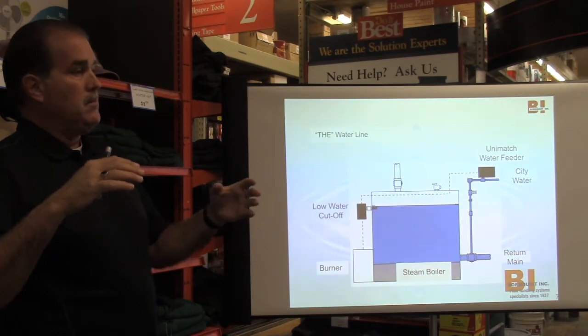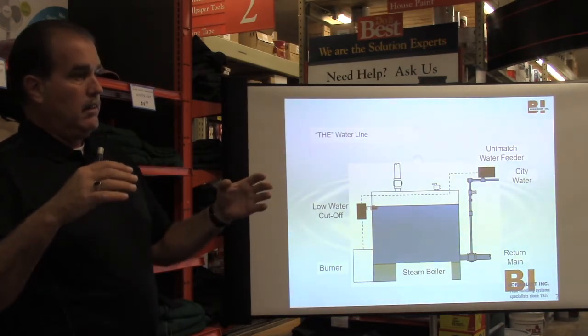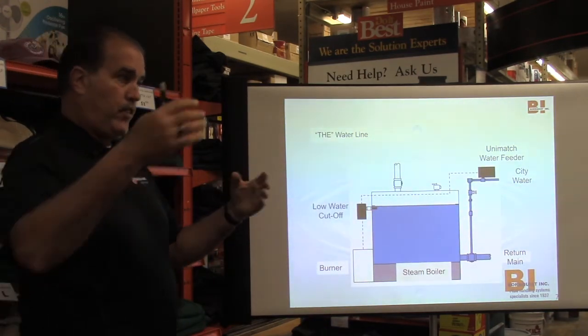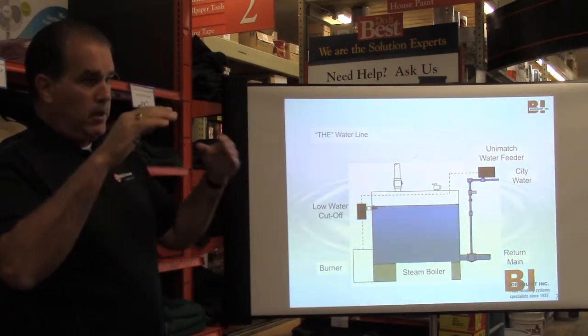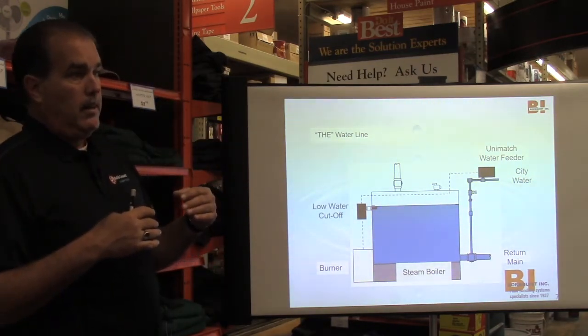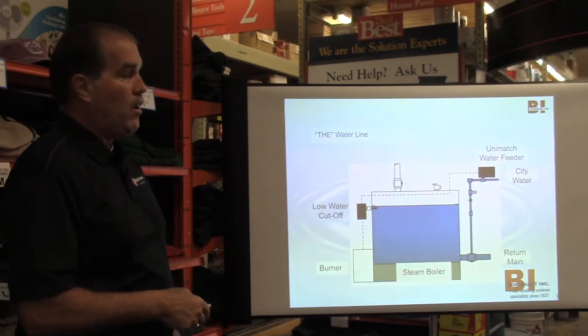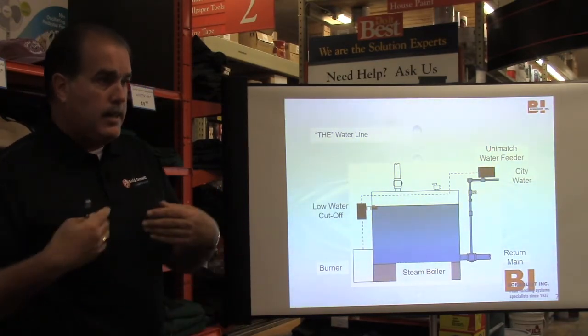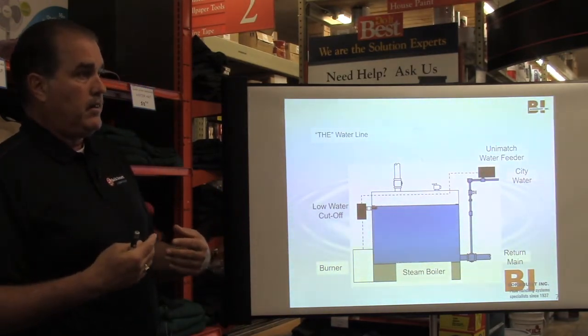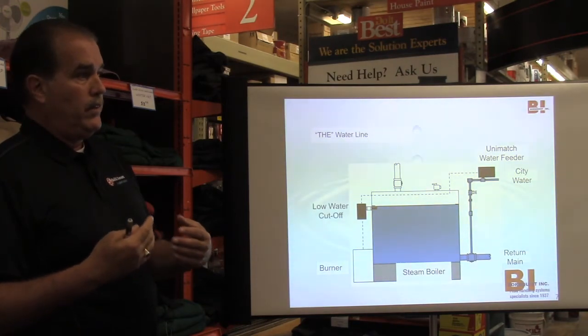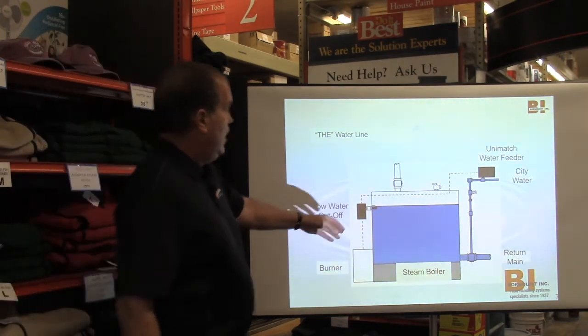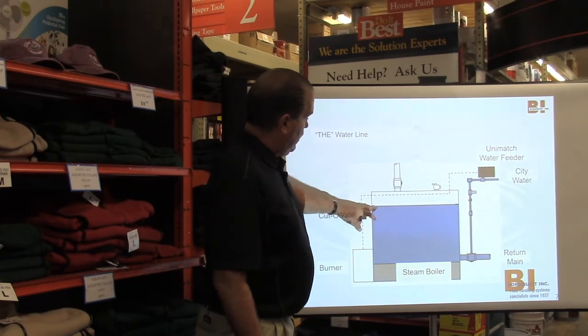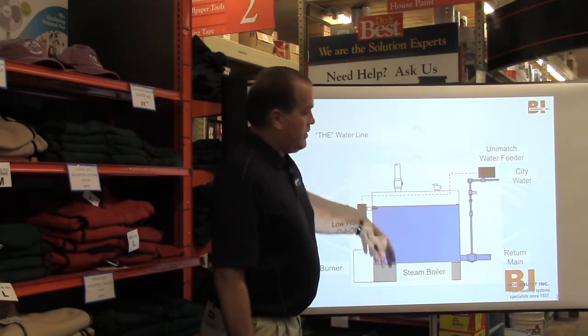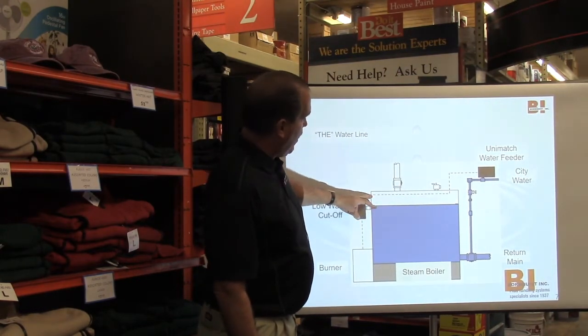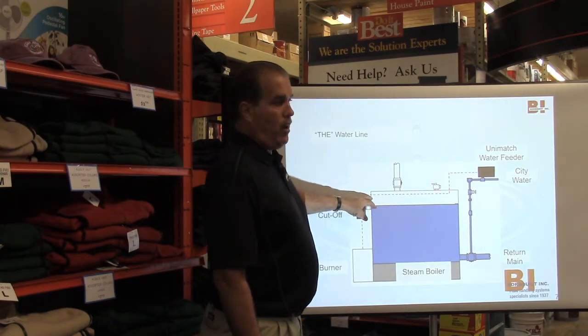Now, sometimes it gets stuck. And for whatever reason, it just can't flow smoothly back to the boiler, but it's slowly working its way back. You don't want to turn your water feeder on until that condensate has a chance to get back to the boiler. If you turn it on too soon, it'll turn off the water feeder here, but then more condensate comes back, and all of a sudden your water line starts rising. So now you've got a high water line.